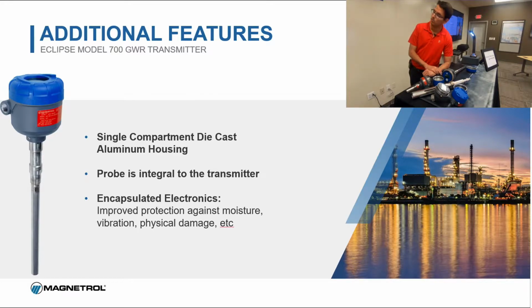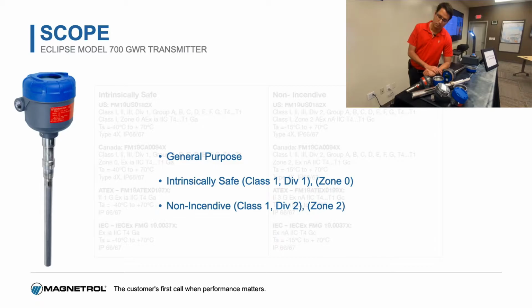All right, so here's one of the limitations, or a couple of limitations. We don't want this probe, as I said, it's more for the commercial and the light duty applications. So it's only available in intrinsically safe and non-incendive. So you don't have the explosion proof options in this enclosure, right? So you've got the equivalent, like the non-incendive rating, class 1 div 2, class 3 division 2, class 1 div 2, and you have intrinsically safe. So you would wire that with an intrinsically safe barrier.